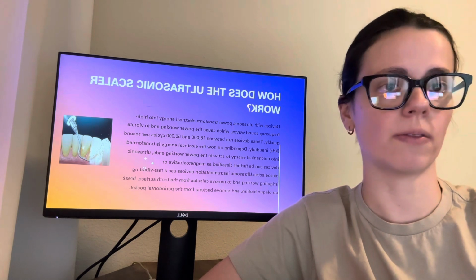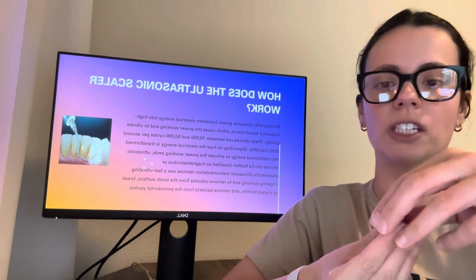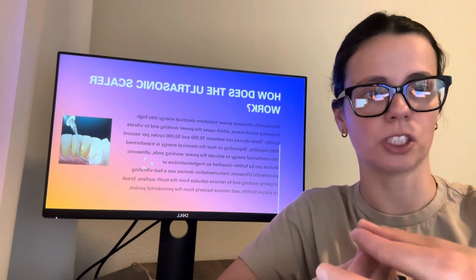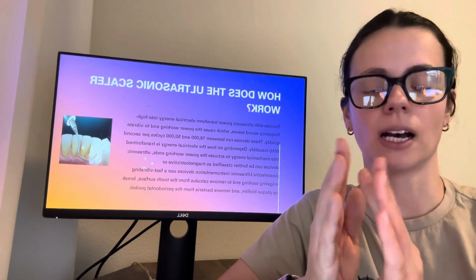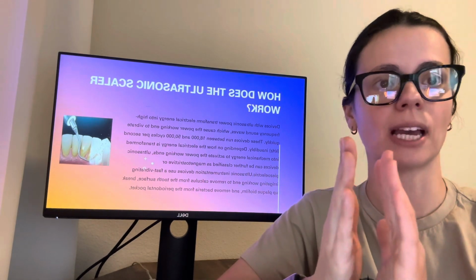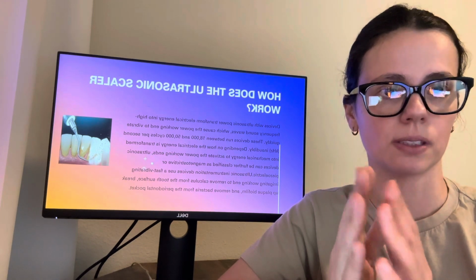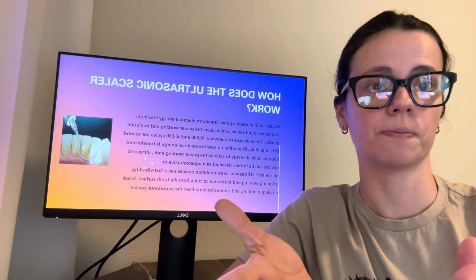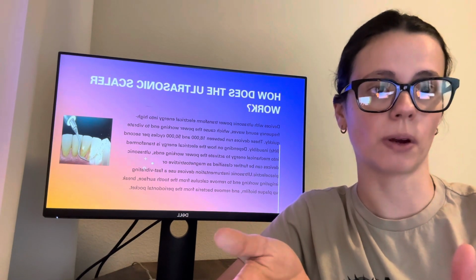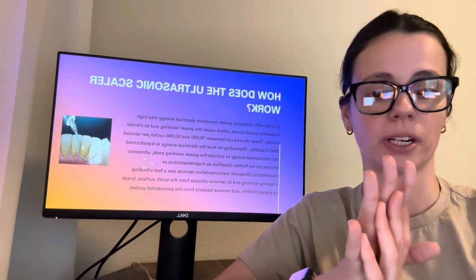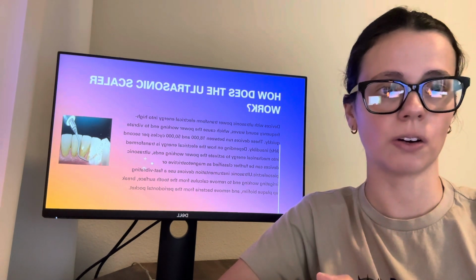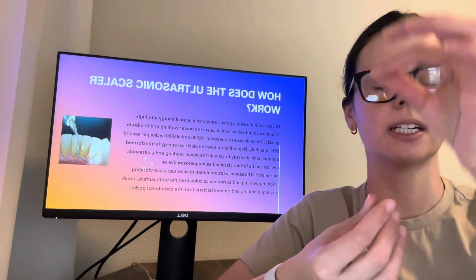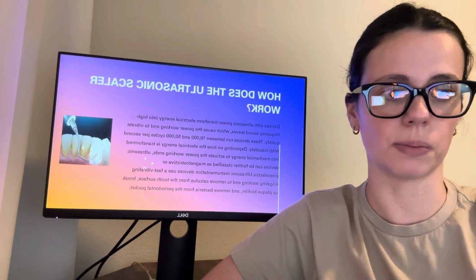So that's why it's important to have water. With the handpiece, we need to fill it up with water all the way up and insert the tip in a vertical way. When these very thin filaments vibrate together, if there are any air bubbles, it's going to get hot and make our instrument hot, and this can cause thermal injuries to the patient. So it's very, very important to make sure we flush our device and fill it up with water all the way before we insert the tip.